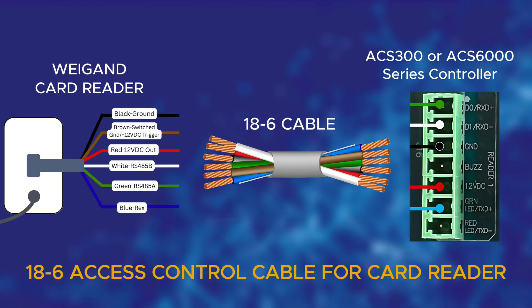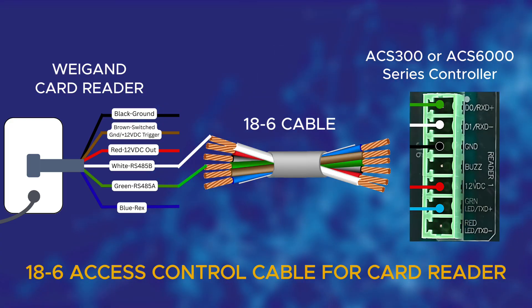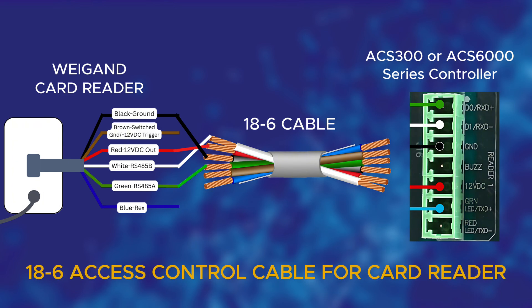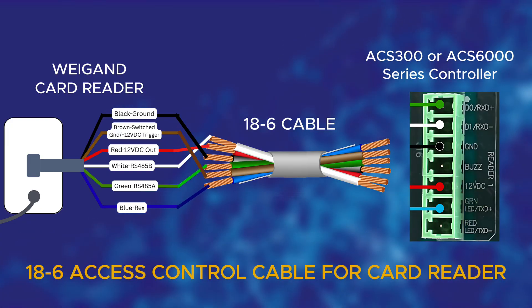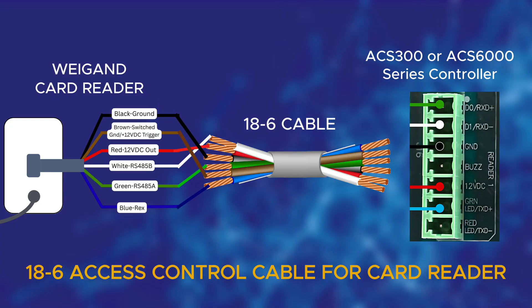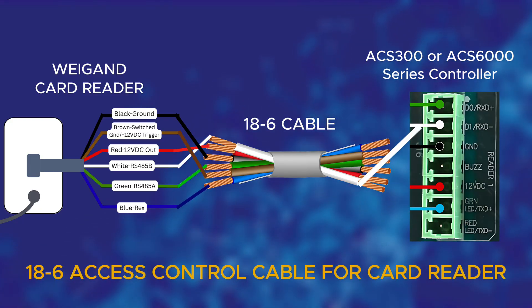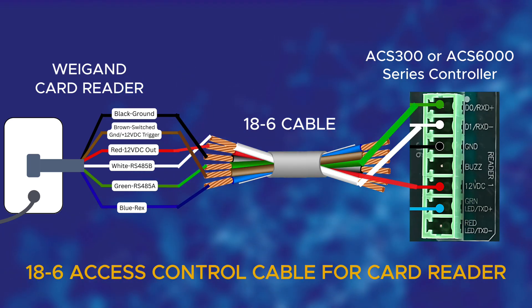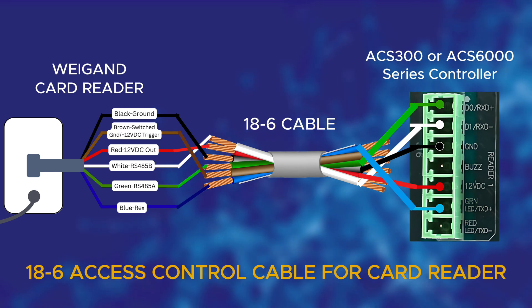Start by matching the wires to their designated functions. The white wire is for RS-485B. The green wire goes to RS-485A. Red is your 12-volt DC power out. Black is for ground. The brown wire is used for a switched ground or 12-volt DC trigger. And finally, the blue wire is for REX, or request to exit. Now let's connect the 18-6 cable to the ACS300 or ACS6000 series controller. Start with the white wire — this connects to D1RXD-. Next, the green wire goes to D0RXD+. The red wire provides 12 volts DC power and the black wire is for ground. Finally, connect the blue wire to the green LED line, which also functions as TXD+.